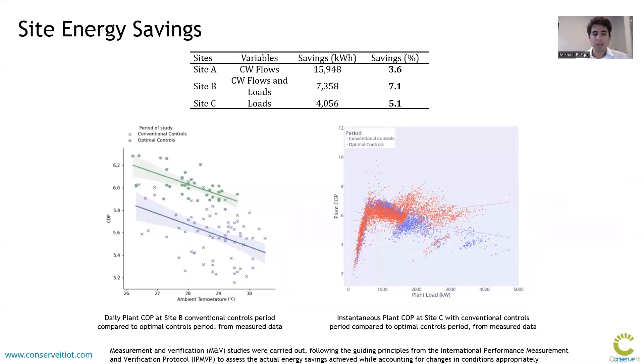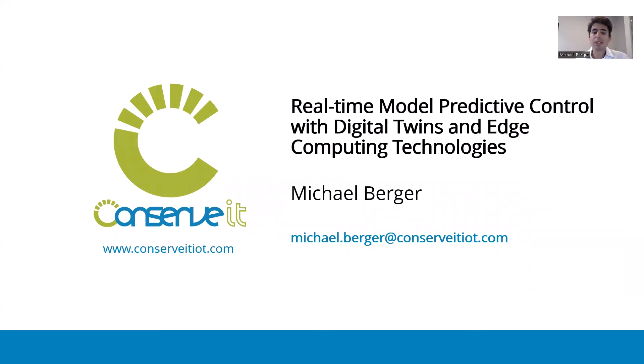Finally, energy savings were computed using measurement and verification studies following guiding principles from the International Performance Measurement and Verification Protocol (IPMVP), which gives guidelines on how to properly account for changes in conditions. Good savings of 3.6% to 7.1% were found depending on the site — quite significant considering no mechanical equipment was changed, only control strategies. The plant COP, a measure of efficiency, was shown to increase with optimal controls for sites B and C. Thank you very much for your time. This was real-time model predictive control with digital twins and edge computing technologies by Conservit.